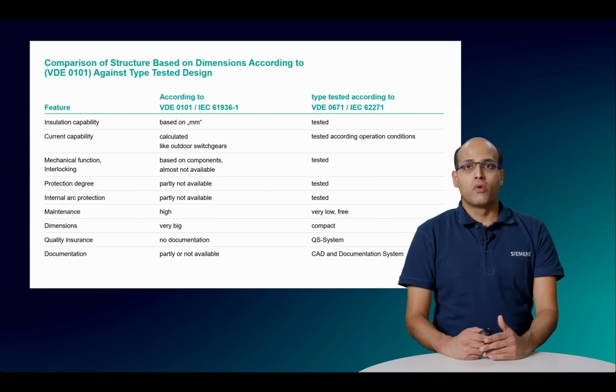As touched upon previously, the modern day switchgears require less maintenance in comparison to the comprehensive maintenance requirements of former times. The quality and safety system, in short QS system, was not properly developed in former times. Today, this comprehensive framework ensures that high standards of quality and safety are maintained throughout the life cycle of switchgear. Finally, the documentation system of today is comprehensive with CAD design and details related to individual components, helping users with operation, installation, maintenance, etc. Such documentation was only partly available or even not available in the former times.